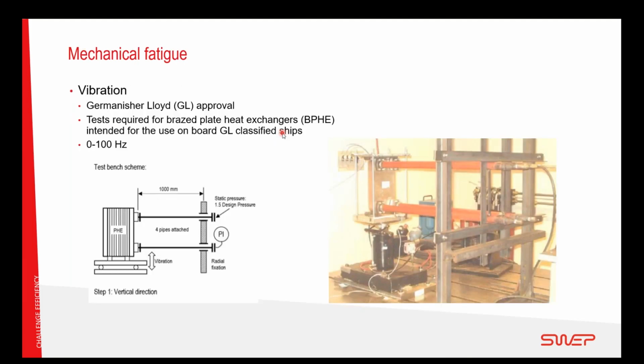Another testing that we have done is from a vibration point of view. There's an approval for a GL, Germanischer Lloyd. This is a specific test that has been designed for brazed plate heat exchangers, that's BPHE, that's intended to be used on board GL classified ships. So it basically is a test where you have the heat exchanger mounted on the shaker itself, and then you have 1 meter long pipes attached to the heat exchanger, and then they are fixed on the other side.